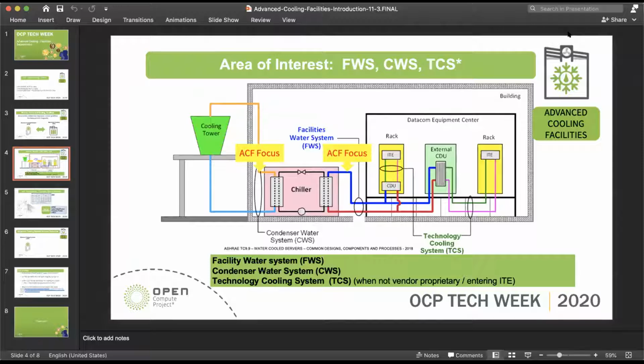Or in some cases, there are data centers that are evaporative cooled right now, and they have a very successful model for evaporative air cooling. They may just want to put in provisions to add a pipe, a pump, and a heat exchanger. And actually, if you think a little further down the path, that heat exchanger, if you're operating at elevated temperature, could easily be, or maybe efficiently be, used for energy reuse and heat reuse.